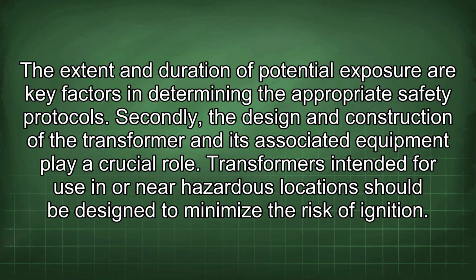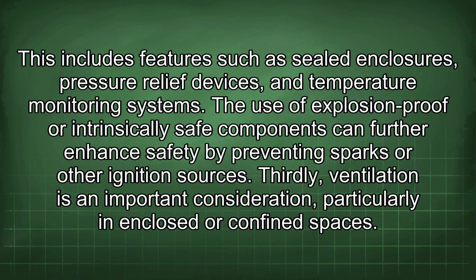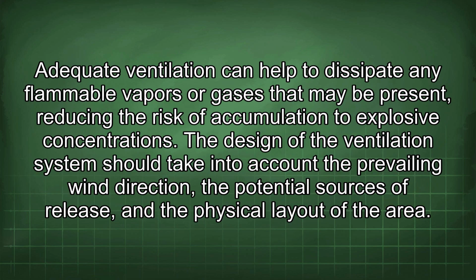Secondly, the design and construction of the transformer and its associated equipment play a crucial role. Transformers intended for use in or near hazardous locations should be designed to minimize the risk of ignition. This includes features such as sealed enclosures, pressure relief devices, and temperature monitoring systems. The use of explosion-proof or intrinsically safe components can further enhance safety by preventing sparks or other ignition sources. Thirdly, ventilation is an important consideration, particularly in enclosed or confined spaces. Adequate ventilation can help to dissipate any flammable vapors or gases that may be present, reducing the risk of accumulation to explosive concentrations. The design of the ventilation system should take into account the prevailing wind direction, the potential sources of release, and the physical layout of the area.